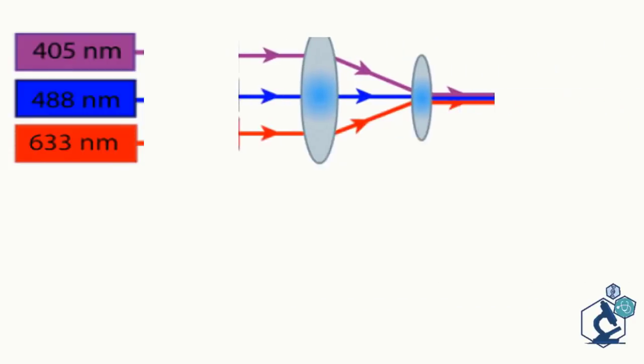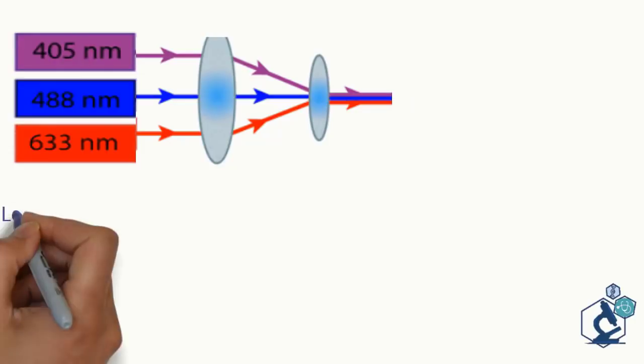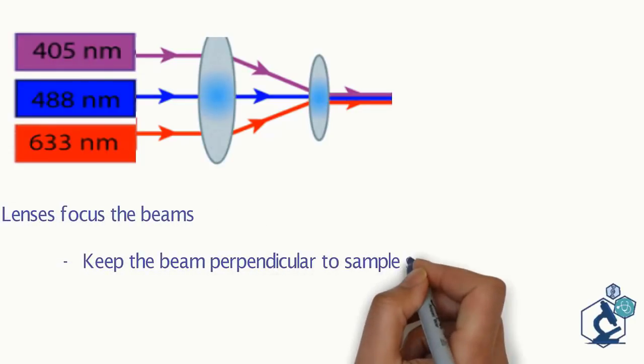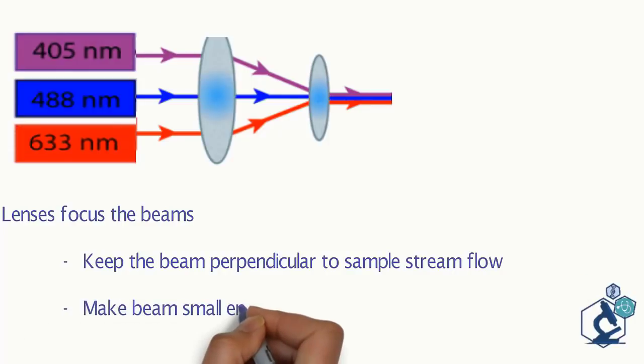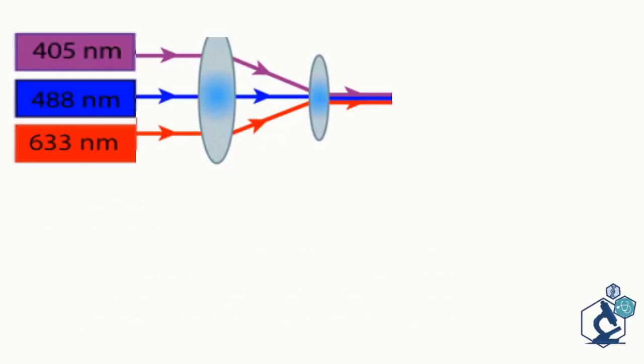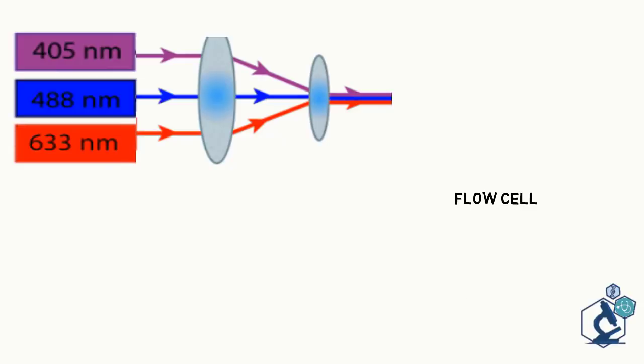Before the laser beams reach the sample stream, crossed cylindrical lenses focus the beams. Focusing keeps the beam perpendicular to the sample stream flow while making the beam small enough to illuminate only one cell at a time. The first lens controls the width of the beam, the second height. The resulting elliptical beam is focused on the sensing area of the flow cell.